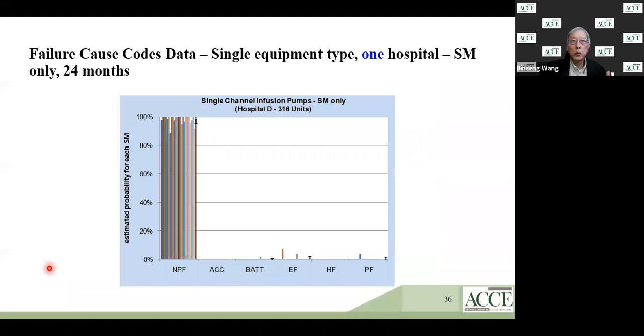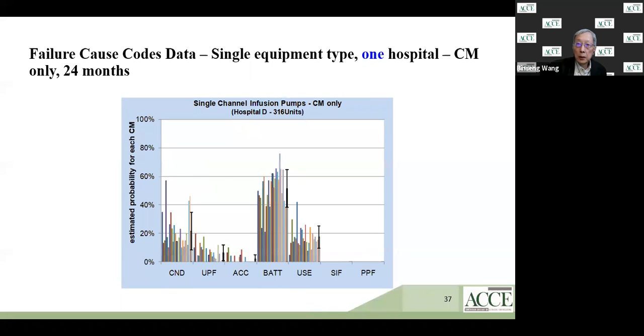Okay, so how do we use this information? Here is an infusion pump, single channel infusion pump, scheduled maintenance only, 24 months. We perform that to see what happens. As you can see, the majority of times we perform scheduled maintenance, we didn't find anything, nothing surprising. Once in a while, we find battery problems, evident failure problems that were not reported by the user, a crack in the door, okay, potential failure, a power cord that's becoming frayed, okay.